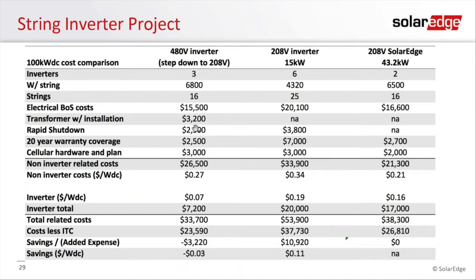So here what we've done is we've looked at 3 different scenarios. We're looking at what is commonly done today, using a traditional 480 volt string inverter paired with a step down transformer, 480 to 208. We're also looking at what is a pretty common building block for a traditional native 208 string inverter, a 15 kilowatt inverter. And then, of course, we have the SolarEdge Synergy 43.2.